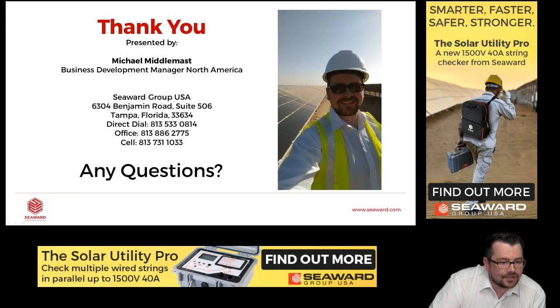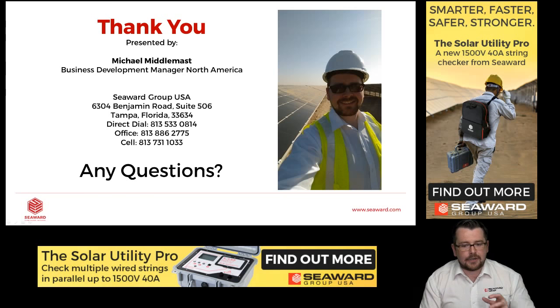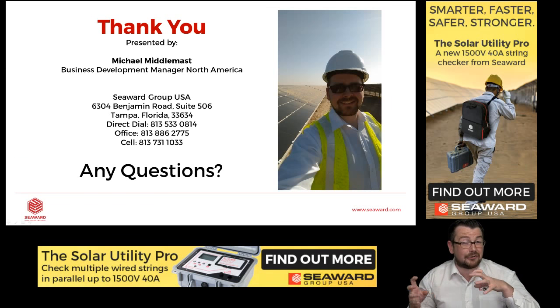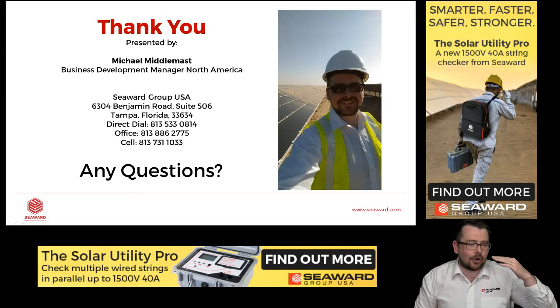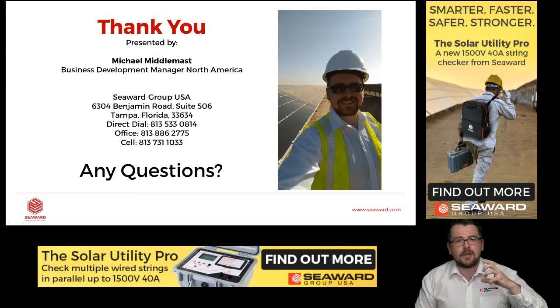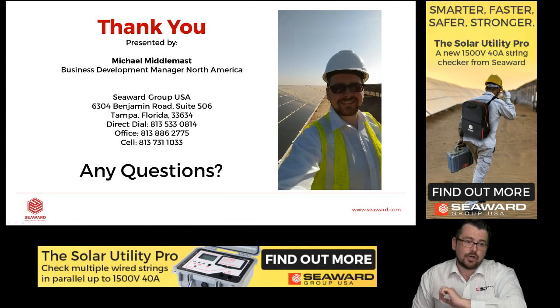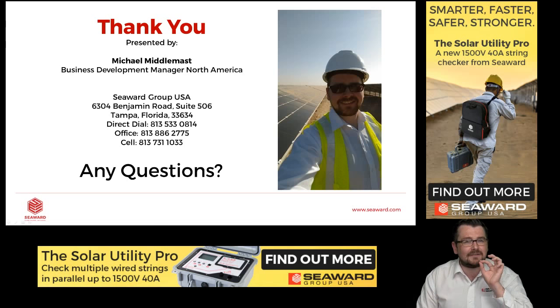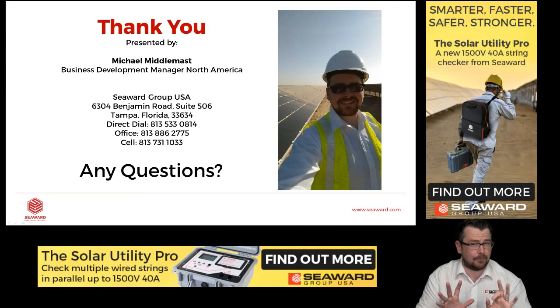Christopher says, what is the industry standard Pmax measurement threshold as a percentage deviation from the manufacturer's specifications to consider a PV string as a pass string during commissioning? Christopher, that's another great question, and one that the industry doesn't have a standard for. It depends on what each manufacturer of panels specifies, and it also depends on what your client will accept. So some will expect a greater margin than others. But I believe, and please don't quote me on this, please do check the standard, I believe 10% is a sweet spot, but you'd have to double check.